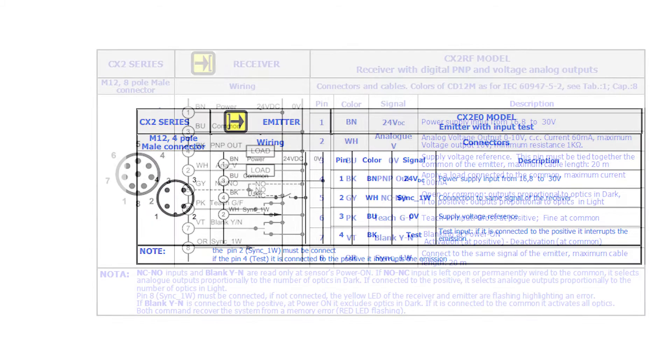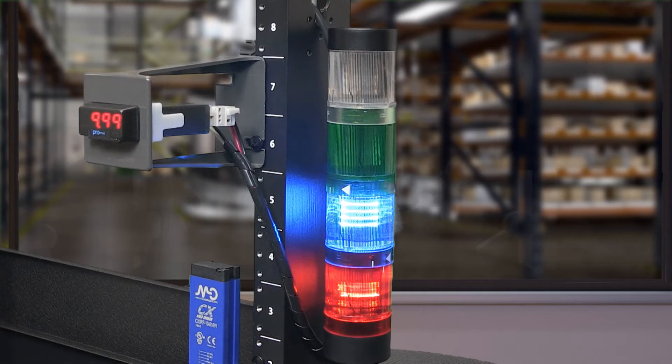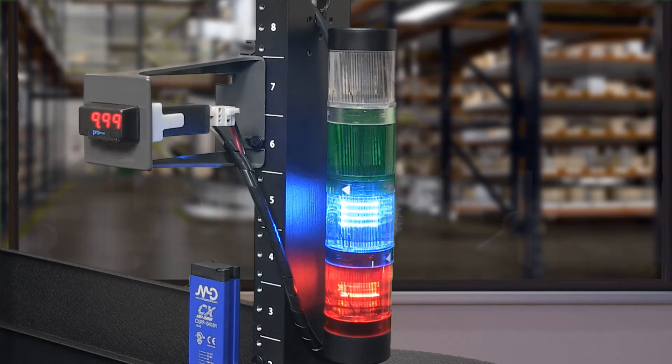Now let's wire the receiver. The receiver has 8 connections — quite a bit, so please pay close attention when wiring to avoid mistakes. Brown is for positive voltage and blue for negative voltage or common to power the sensor. The black wire on the receiver should be connected to your output device and wired as PNP. In this example, I have the black wire connected to the positive input on a Werma stack light that we sell here at AutomationDirect.